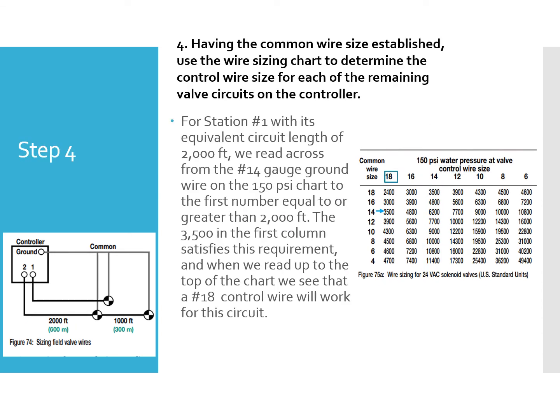Now that we've determined the worst case scenario with station 2 and its 5,000 feet of equivalent circuit length, we can move on to all the other valves. And in this case, there's just one more valve. So since we've already determined that we're going to have a 14 gauge common wire, now we need to figure out what size control wire we can use for that first valve.